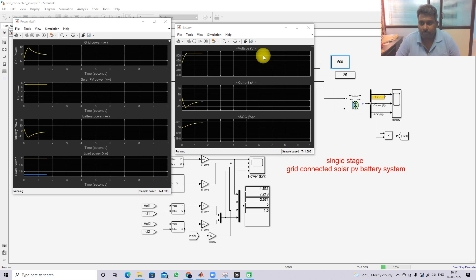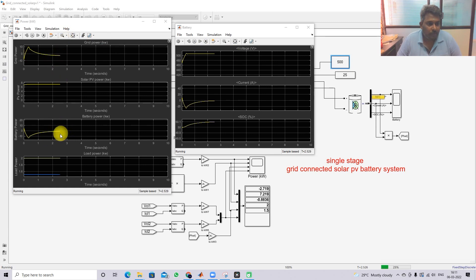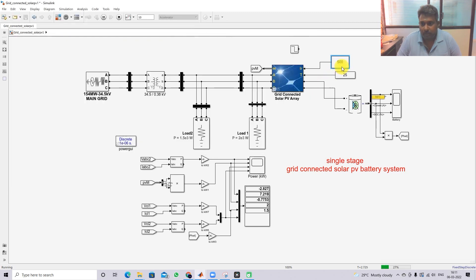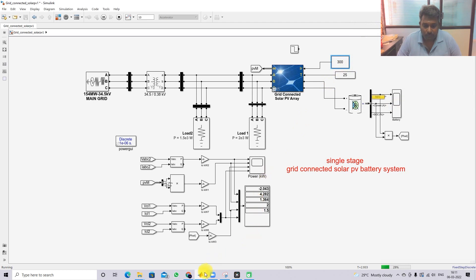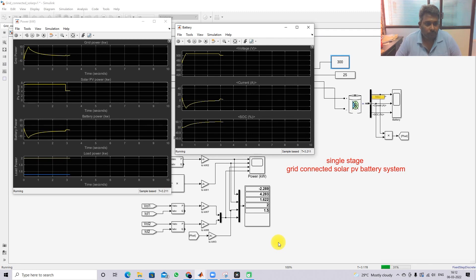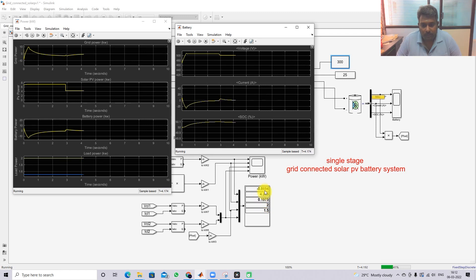Now changing the irradiation from 500 W/m² to 300 W/m² to check the system response. At 300 W/m², the solar PV power is around 4.28 kW. The PV is still supplying power to the load as well as some power to the grid, and the battery continues in charging mode.